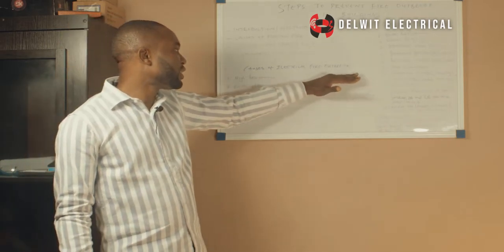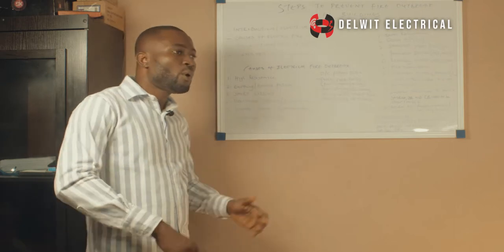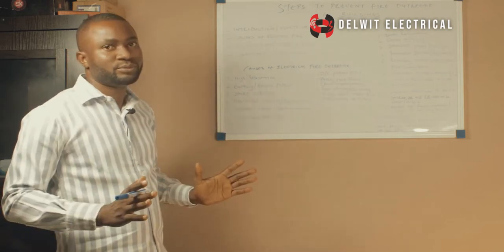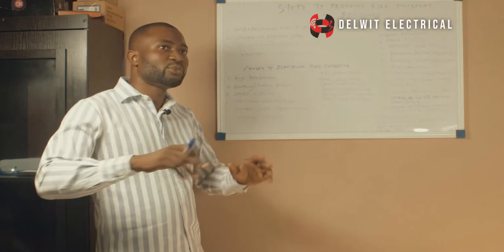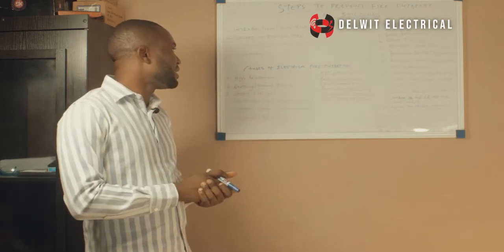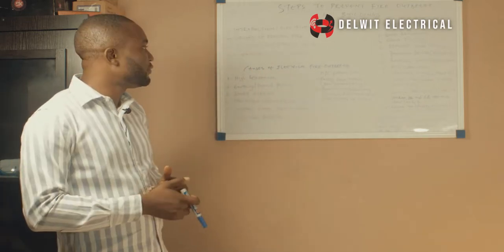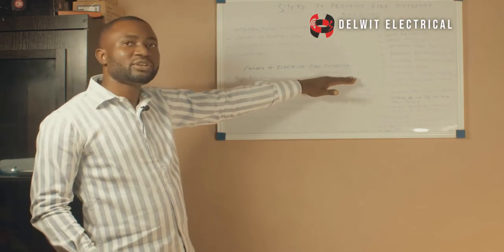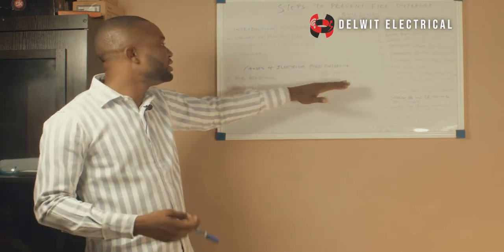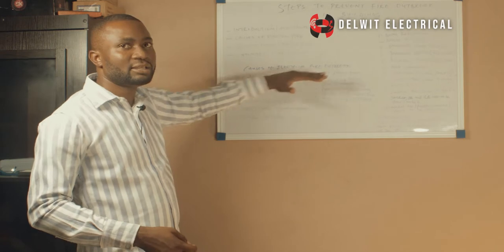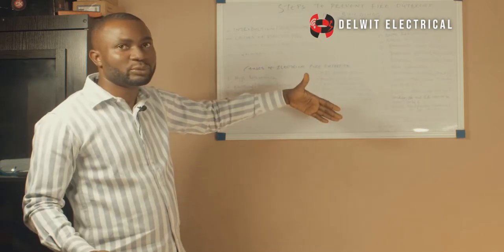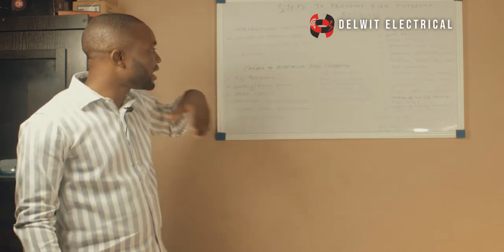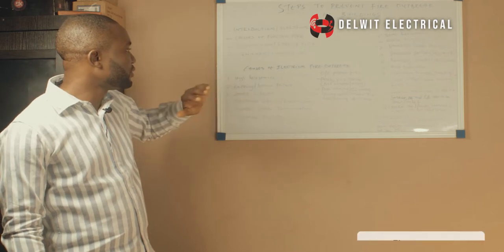We have the open circuit protection failure. Now, all circuits have protection. If you go to your distribution board in your building, you see there's a circuit breaker there. So whenever there is an open circuit failure, if your protection devices have failed, it will lead to high resistance, and in that case, it will lead to damage, and if it's not eliminated, it will lead to fire outbreak. So this is one of the major causes of fire outbreak.